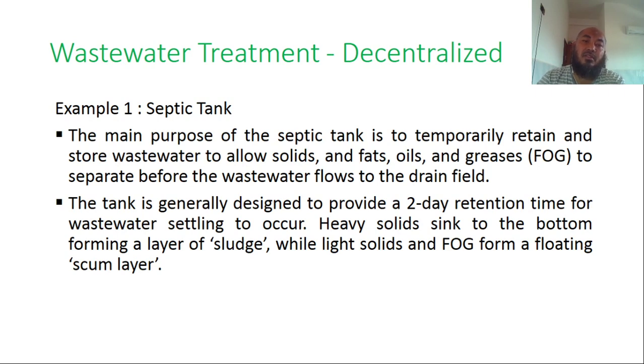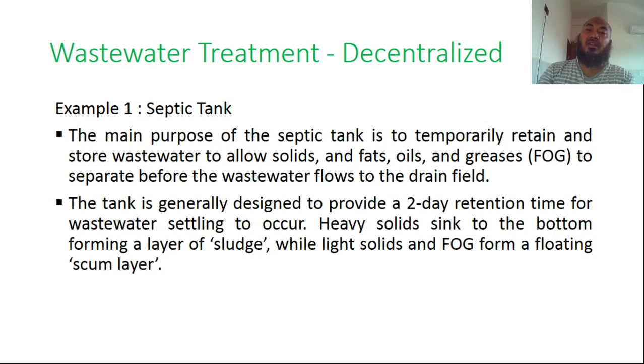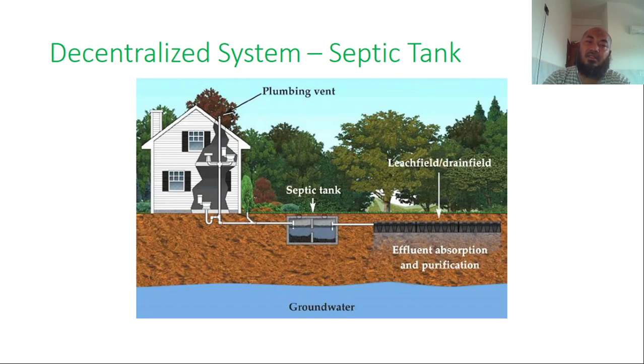In a decentralized setting, we can use a septic tank. The main purpose of a septic tank is to temporarily retain and store wastewater to allow solids and FOG — fat, oil, and grease — to separate before the wastewater flows into the drain field. The tank is generally designed to provide a two-day retention time for settling. Heavy solids sink to the bottom forming a sludge layer, while light solids and FOG form a floating scum layer on top.